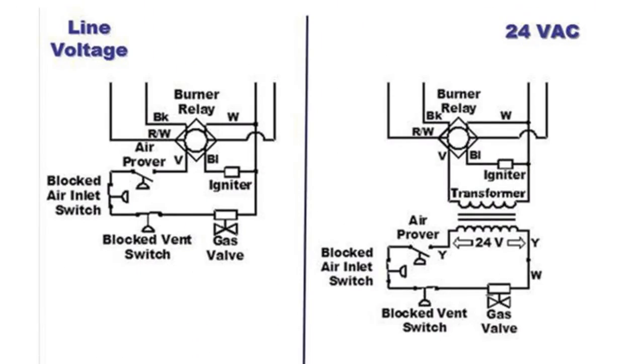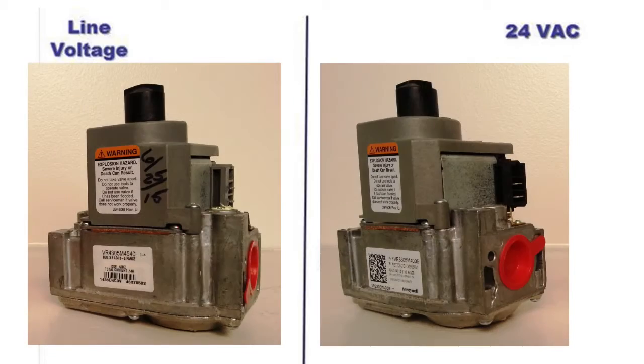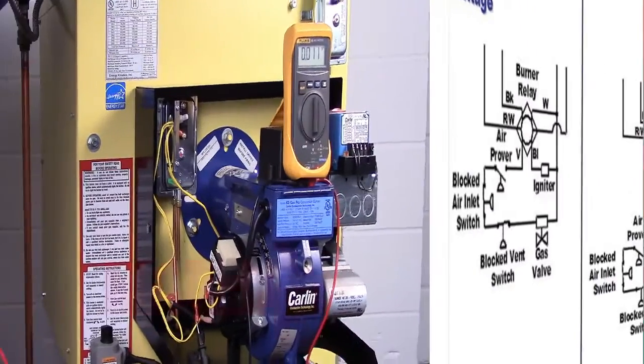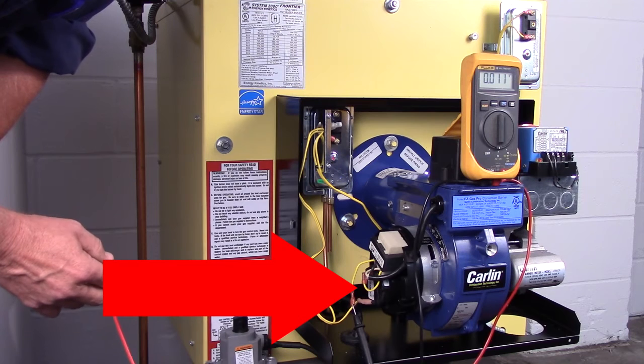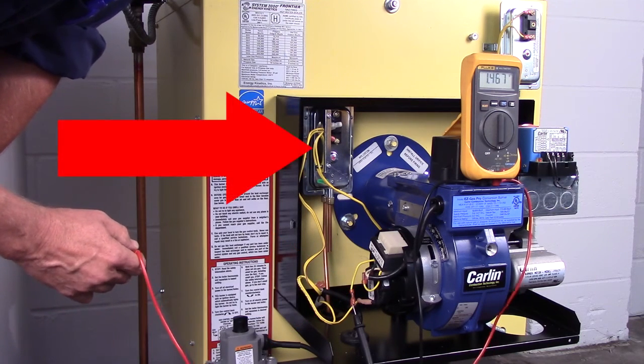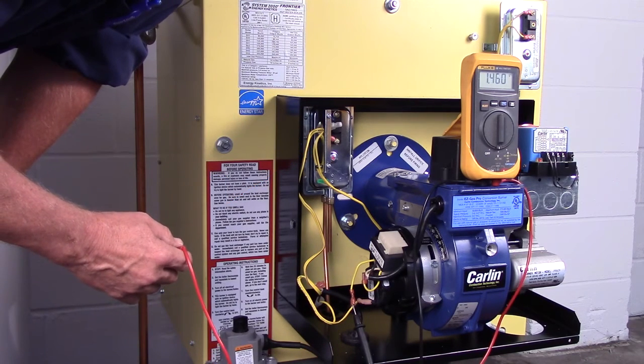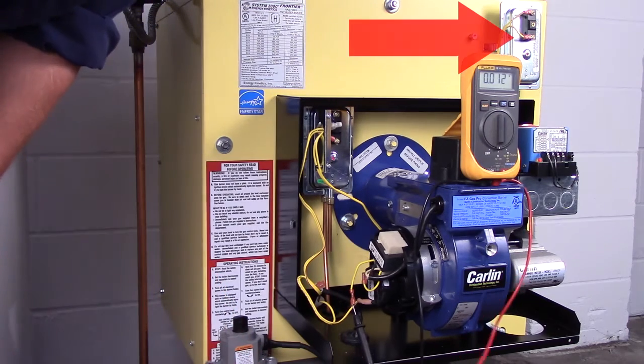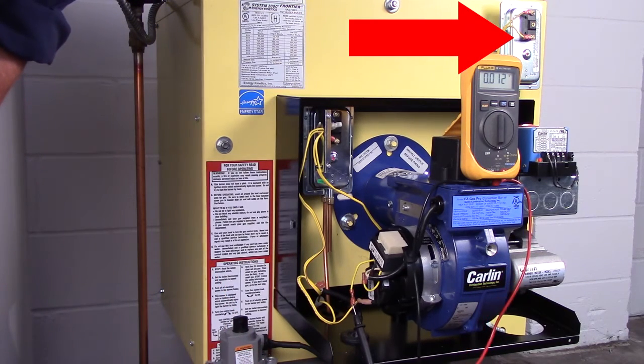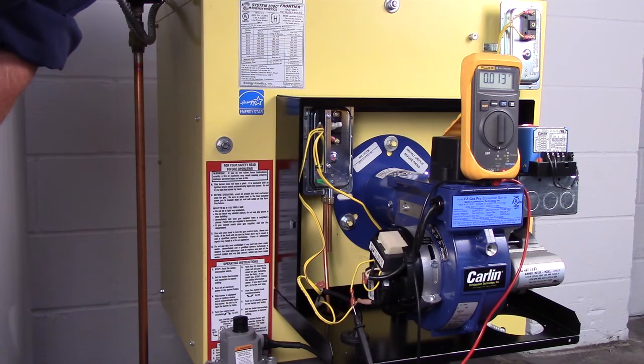The series safety switch circuit is the same on burners with the 120 volts AC gas valve, but without the transformer. The burner airflow switch is normally open and will close when the burner fan operates. The blocked air inlet switch is normally closed and will open if the air intake becomes restricted. The blocked vent switch is normally closed and will open if excessive back pressure exists in the boiler or vent system. So check for flue blockage or air infiltration into the flue.